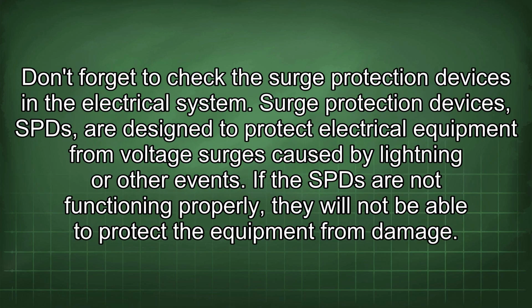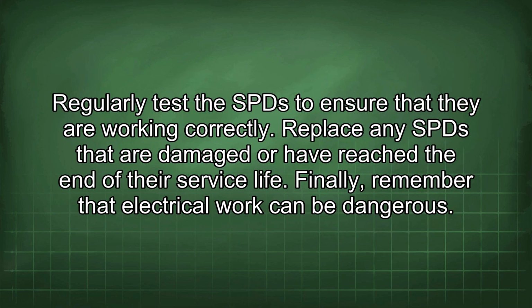Don't forget to check the surge protection devices in the electrical system. Surge protection devices, SPDs, are designed to protect electrical equipment from voltage surges caused by lightning or other events. If the SPDs are not functioning properly, they will not be able to protect the equipment from damage. Regularly test the SPDs to ensure that they are working correctly. Replace any SPDs that are damaged or have reached the end of their service life.